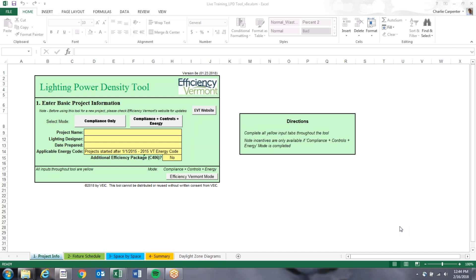New construction projects in Vermont must meet the 2015 Commercial Energy Code. The Commercial Code has maximum allowed power levels for each room type, calculated in watts per square foot for each space. Efficiency Vermont created a Lighting Power Density Tool that includes all relevant code requirements. This tool compares the actual installed wattage to the code max wattages, occupancy and dimming controls to the code, daylighting controls to the code if they are included, and exterior lighting power to the code.